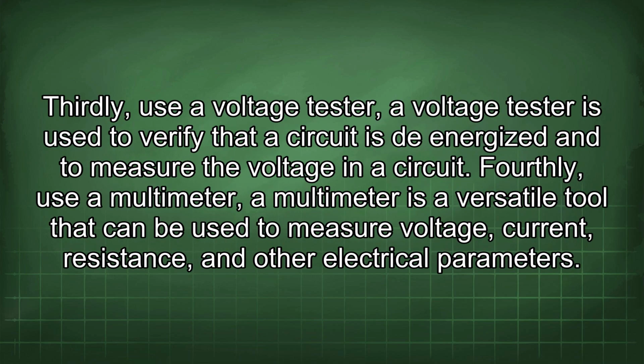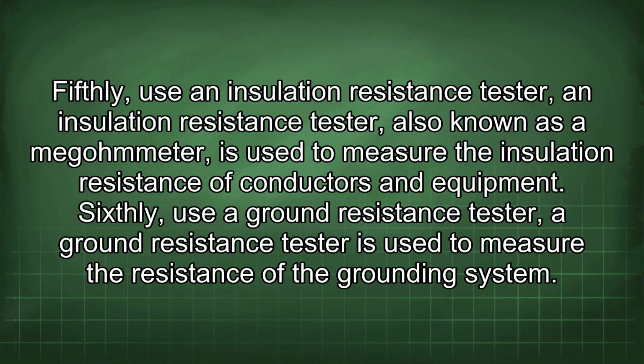Thirdly, use a voltage tester. A voltage tester is used to verify that a circuit is de-energized and to measure the voltage in a circuit. Fourthly, use a multimeter. A multimeter is a versatile tool that can be used to measure voltage, current, resistance, and other electrical parameters. Fifthly, use an insulation resistance tester. An insulation resistance tester, also known as a megohmmeter, is used to measure the insulation resistance of conductors and equipment. Sixthly, use a ground resistance tester. A ground resistance tester is used to measure the resistance of the grounding system.